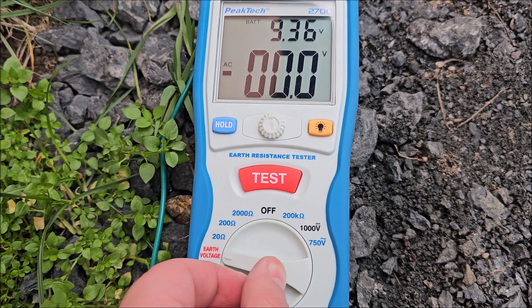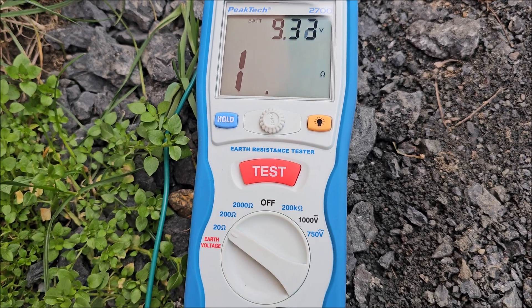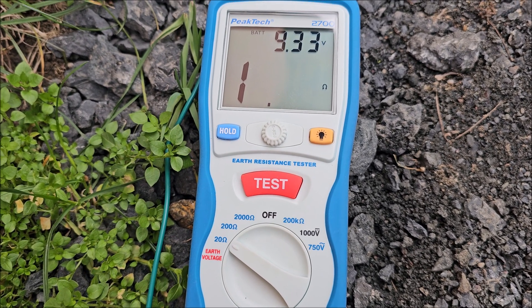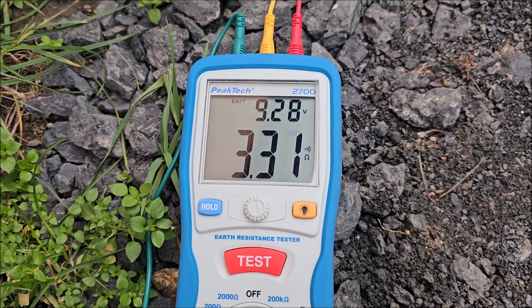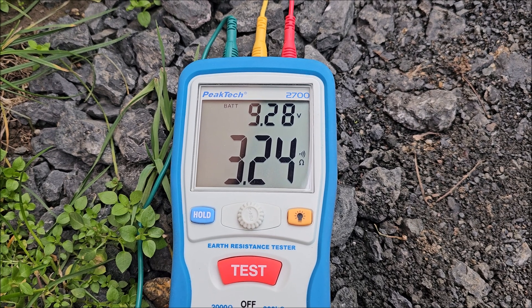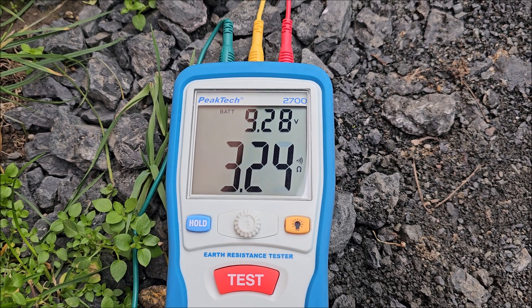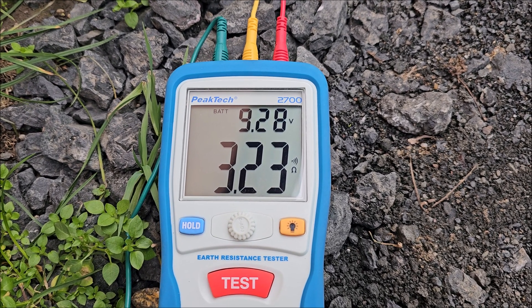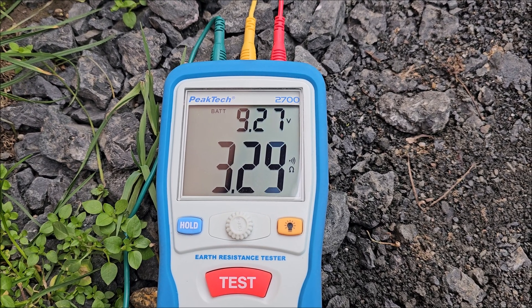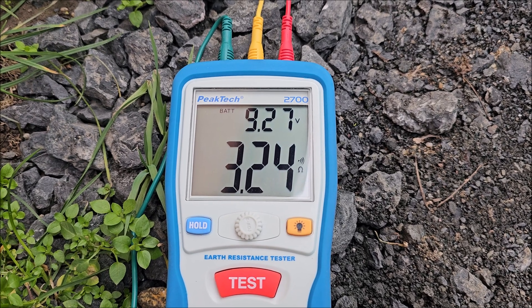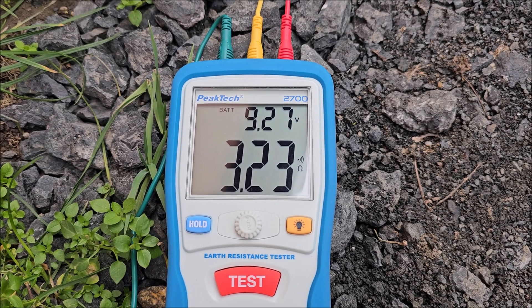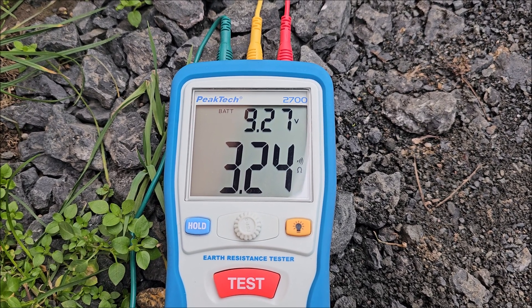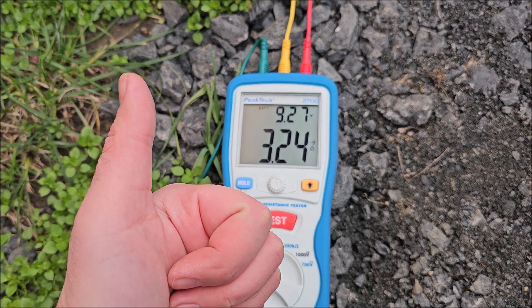I don't know, I'm going to do that at the end, I'm going to just connect them again to make sure that everything is fine. But for the moment I think we can actually do the test itself. So in theory we have 3.24 ohms, which is below the 4 ohm limit that I need to have for the solar panels. Great.